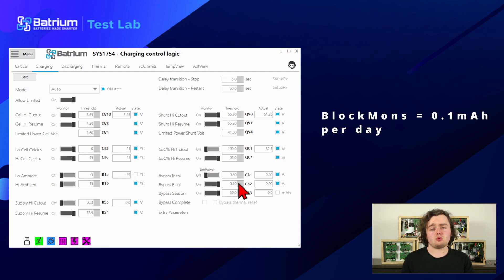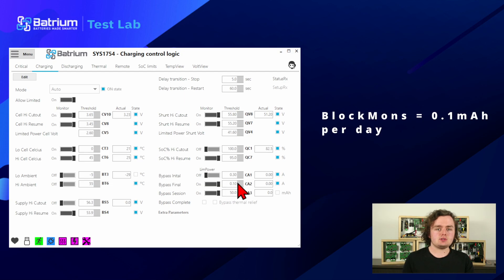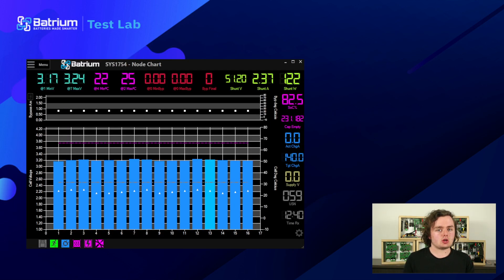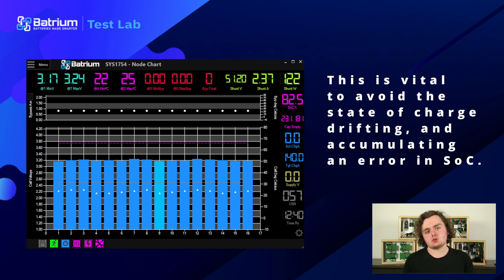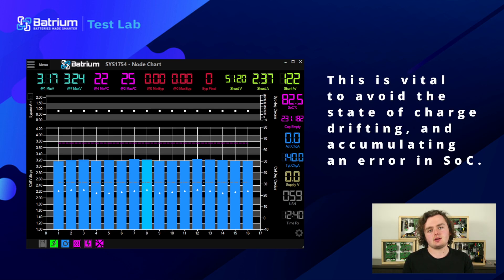It's a really important point to reach bypass complete, as it resets the state of charge to 100% and also signals the inverter that we're done. It's vital to avoid the state of charge drifting due to small inaccuracies adding up over time.